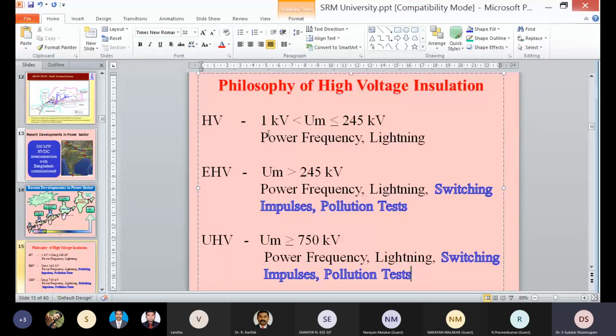I repeat, every level of voltage has its unique nomenclature. When it comes to a high voltage line, that is less than 245 kV, we are not considering switching impulse voltage. We are considering only power frequency and lightning. Why, I will explain to you.